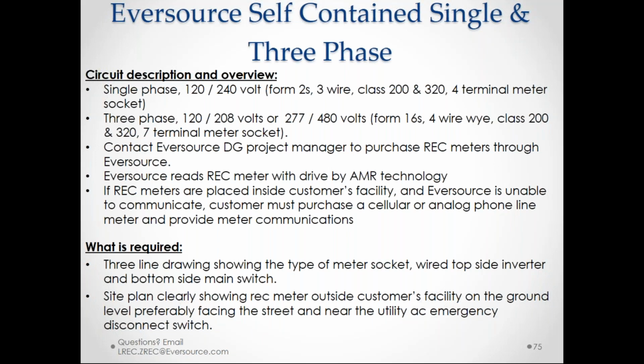And when you go to those IT-rated meters, that's when you are required to purchase the CTs yourself, and in the case of the 480-volt situations, also purchase the VTs yourself. So you will communicate that through someone like myself, the DG project manager, for purchase of the meter.